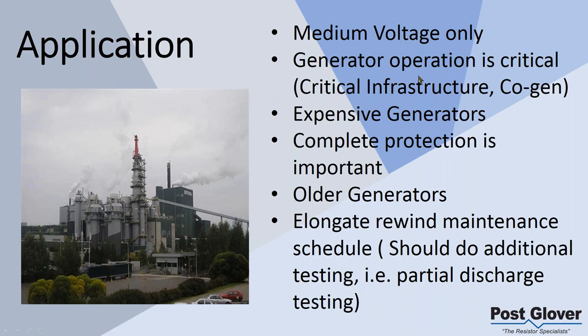So let's say your generator operation is critical. You have critical infrastructure, you have cogen. What happens if you have a stator fault? You have downtime, which is not acceptable. Now you may have stuff built in. If you have 2 generators, if you have complete redundancy, you just have to consider that. But if you don't have enough of it, you might want to use this for the added protection. You're not going to have 0 downtime, because if you get a stator fault, you're going to have downtime, but you're going to drastically reduce the downtime you potentially could have.